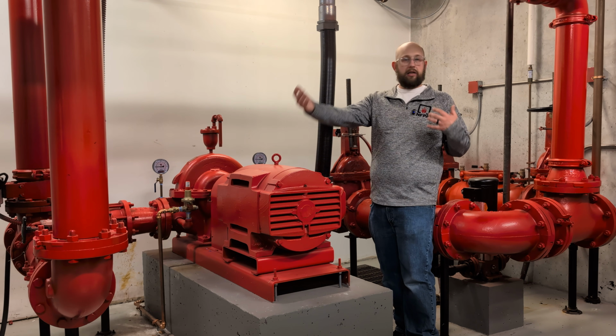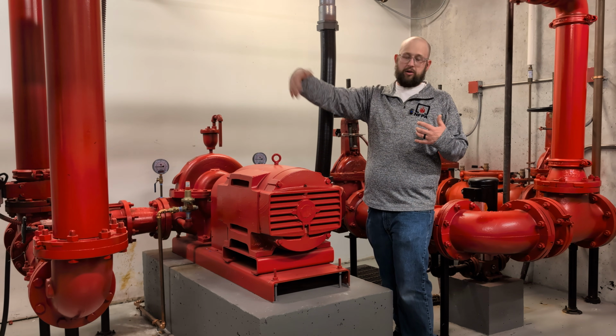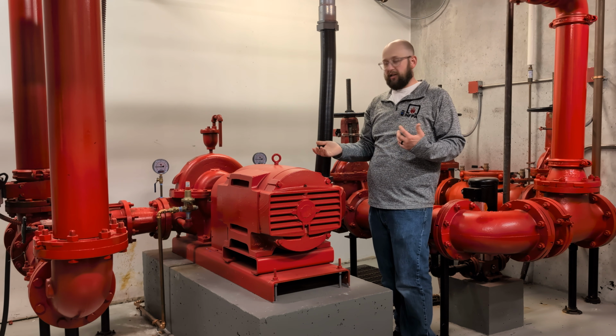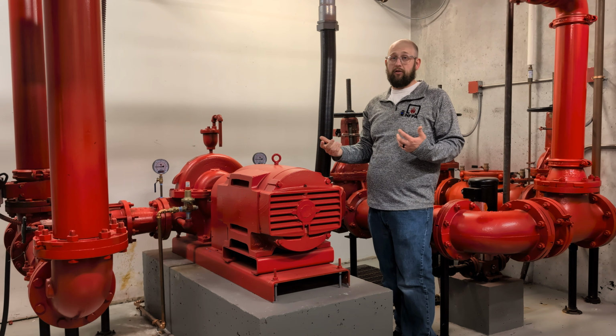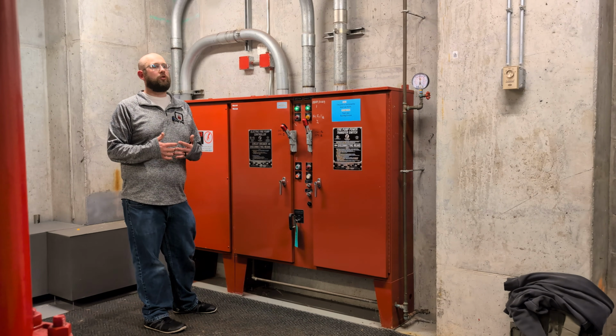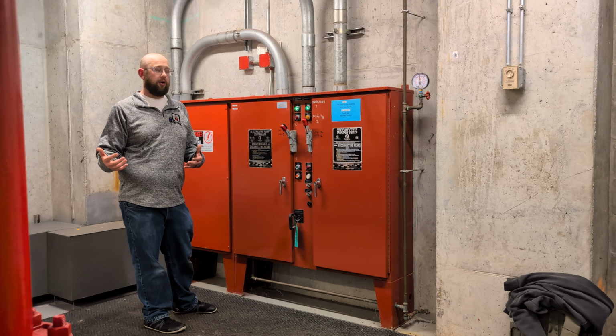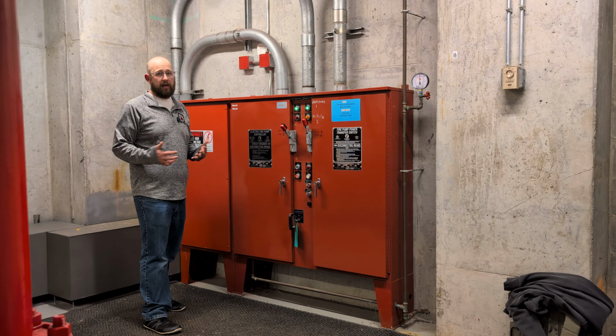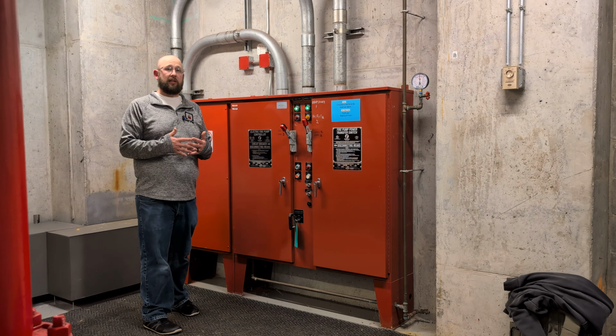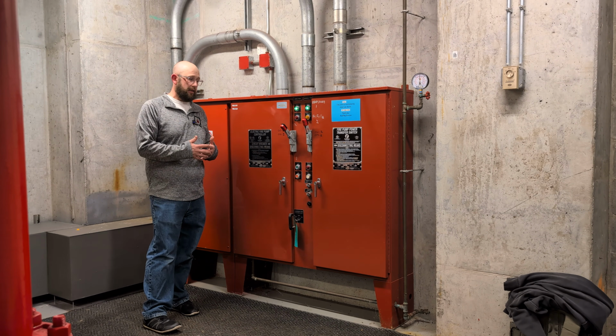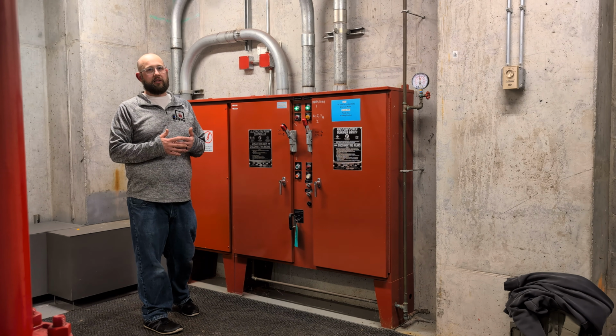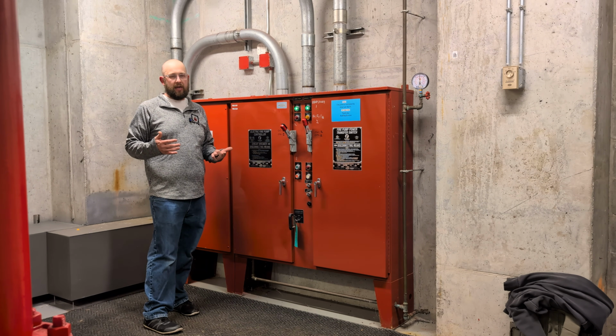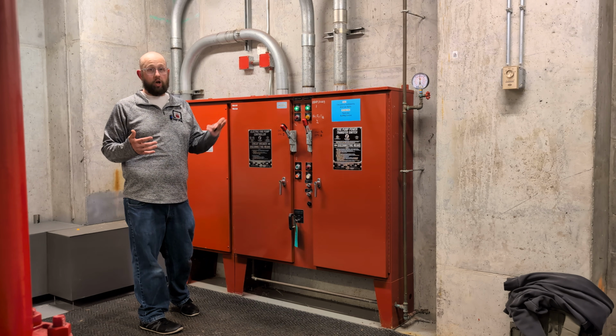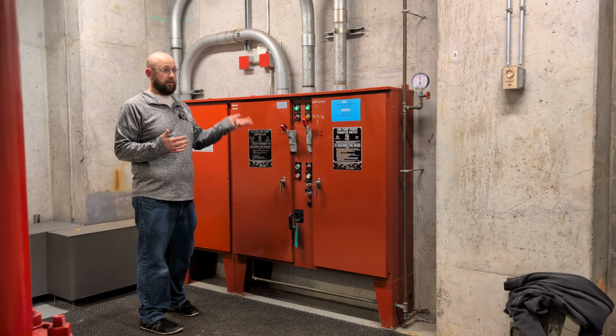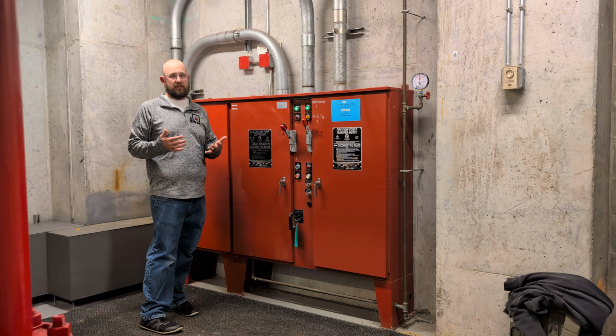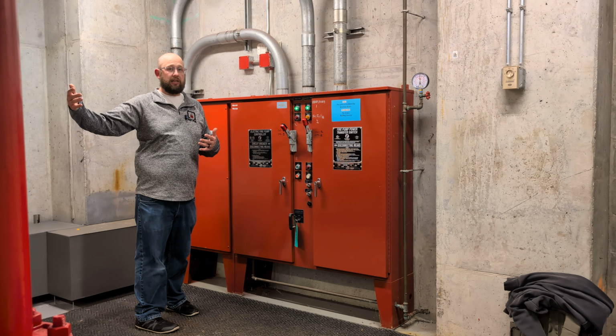Obviously, the fire pump's supplying a system, so the system, whether a sprinkler or a standpipe, is going to have its own inspection, testing, and maintenance, but that's just a little overview of what we're doing for the fire pump itself. So someone asked, what do we need to monitor on the fire pump itself? And NFPA 20 requires that we monitor the fire pump through sending signals to a constantly attended location. So for an electric fire pump, we're going to monitor for things like phase reversal or loss of phase, or running on the alternate source of power, or the disconnecting means being open, or the fire pump itself running. So we need to send that to a constantly attended location.